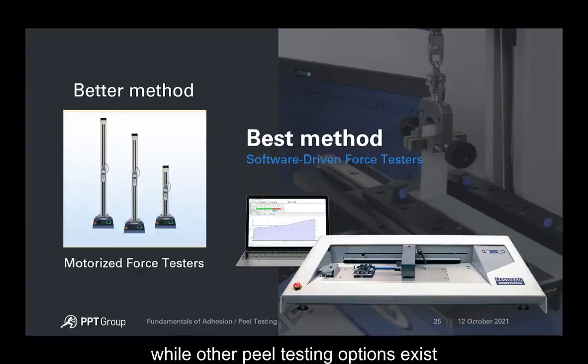So while other peel testing options exist, the option that we highly recommend for this specific application is a software-driven tester. Software-driven testers allow you to not only configure and run the test, but also perform the necessary calculations for any specific industry standard or internal standard. Additionally, you can limit the operator to pretty much positioning the specimen in and out of the fixture and pushing the start button. That's all they need to do.